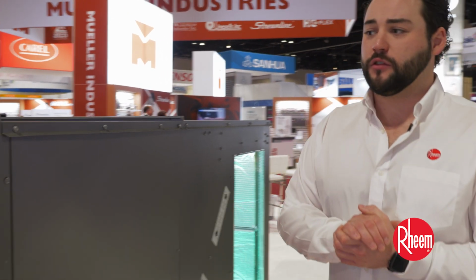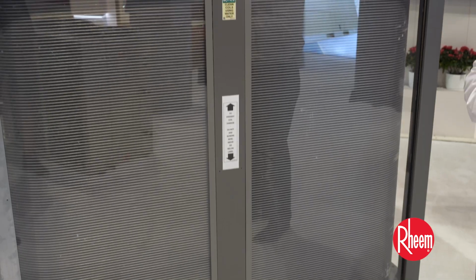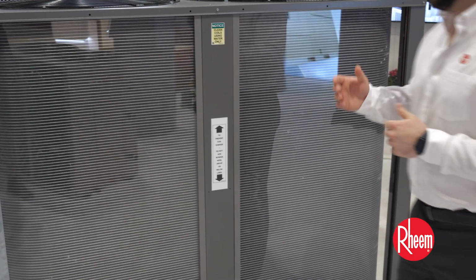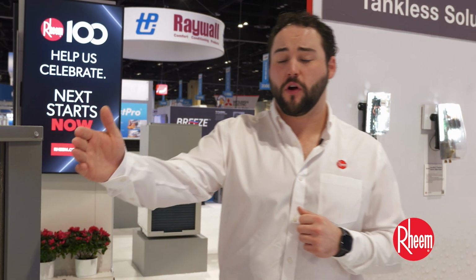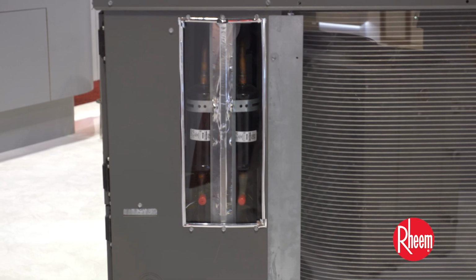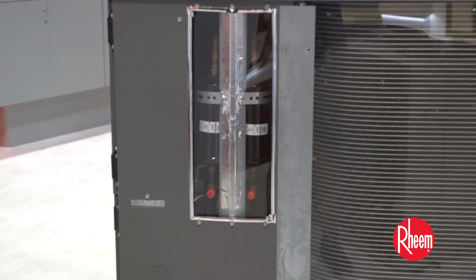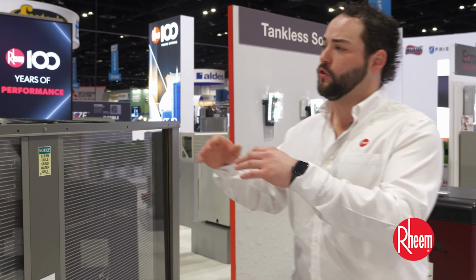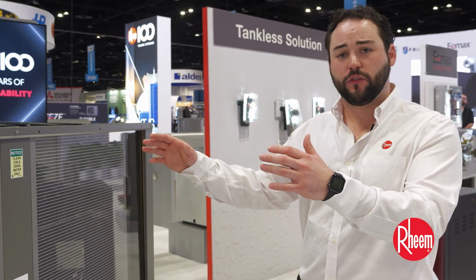Moving on to our condenser section, you will notice that we have a micro-channel coil. What this allows us to do is to have a more efficient heat exchanger. It's lighter and we use less refrigerant in the field. Moving to the far side of the refrigerant circuit, we have our quick access ports for the contractor to actually measure their subcooling and superheat without having to remove too many unnecessary parts within the condenser section.